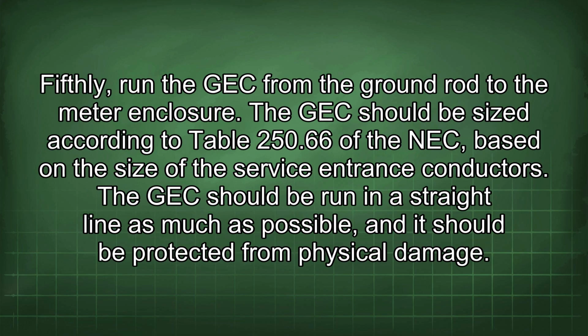Fifthly, run the GEC from the ground rod to the meter enclosure. The GEC should be sized according to Table 250.66 of the NEC, based on the size of the service entrance conductors.